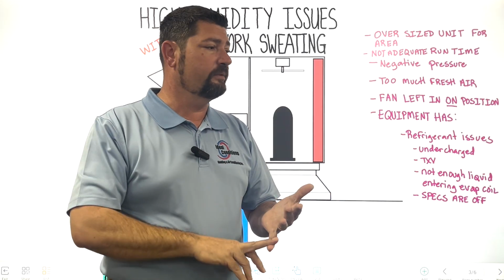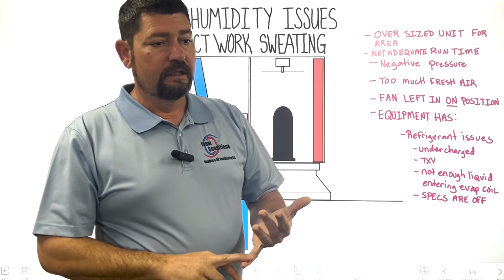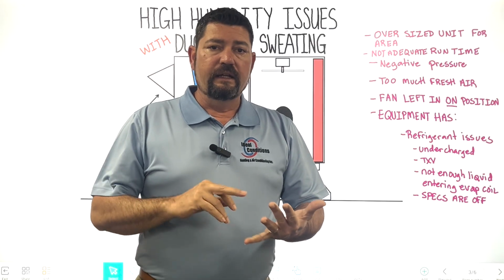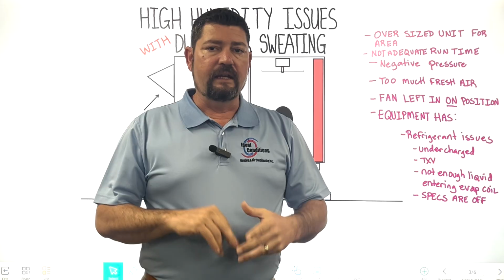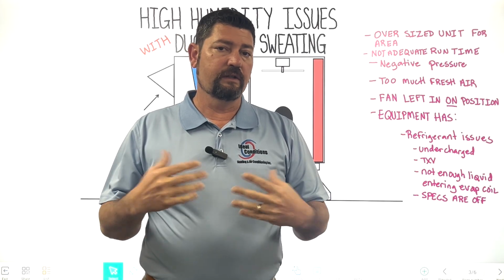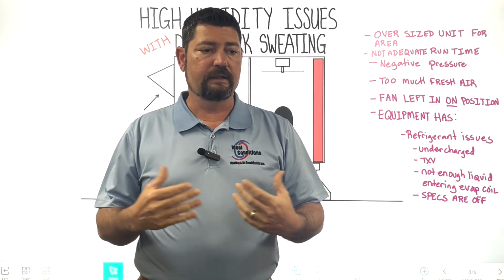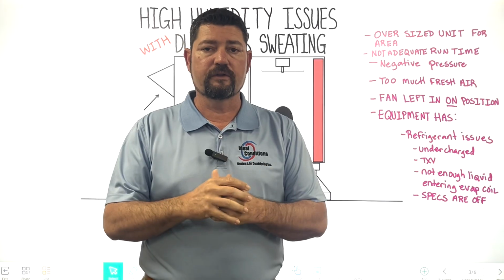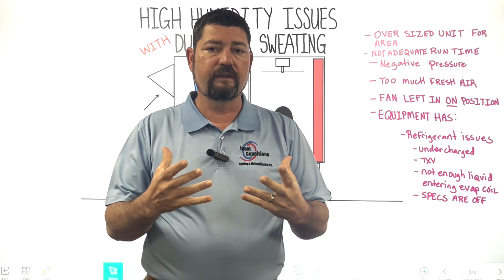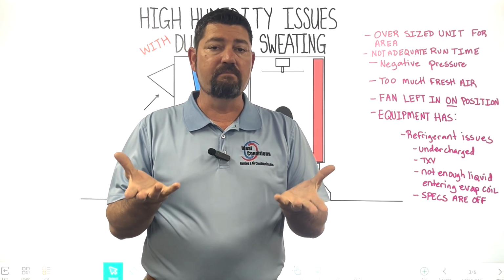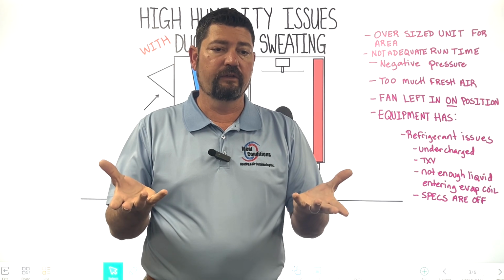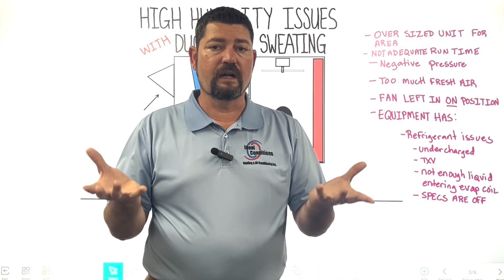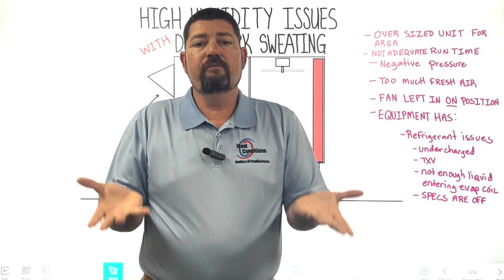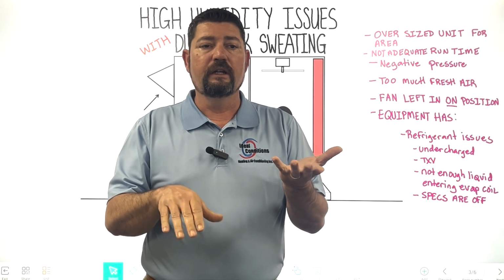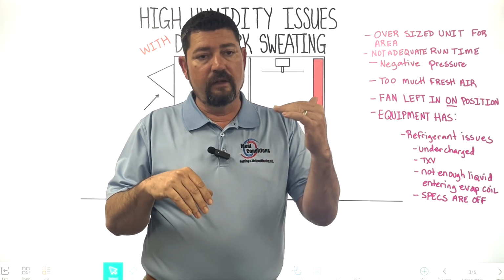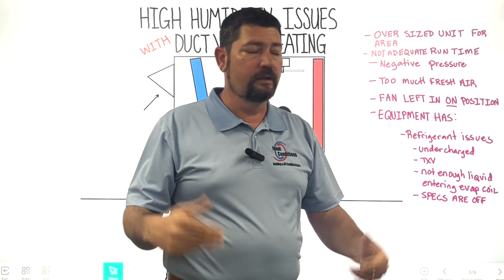So that's the beams that are above the ceiling grid, any steel beams, anything metal. If your ductwork is exposed, if you have something nice like some spiral ductwork or something of that nature, grills, anything that has a metal surface, that metallic surface is going to form condensation on it because the humidity is high and the temperature is low. And the moment we form condensation, eventually it's going to fall, just like when it rains, right?